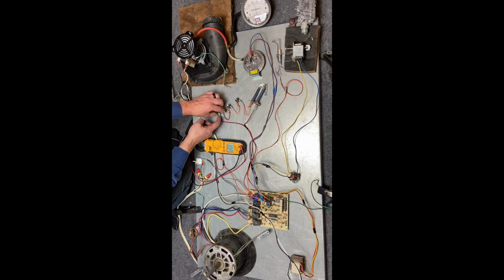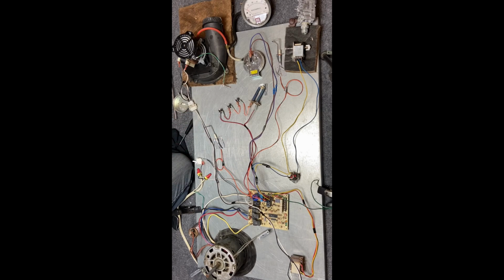Now an easier way is you can just simply press the button and it resets it. So if we check across, we see that we have now 0 volts. So the switch is now closed. Faster way, instead of checking each individual one, you would just simply press all of those and make sure that they are all closed. You do this the same way. You can check voltage. If you're reading voltage, that switch is open. If you're not reading voltage, that is closed. Now again, if you have a main limit switch that fails, you need to be thinking airflow. But it is possible for water to leak from the evaporator coil and cause these to completely corrode up. So everything is simply 2 wires, 2 wires, and 2 wires.